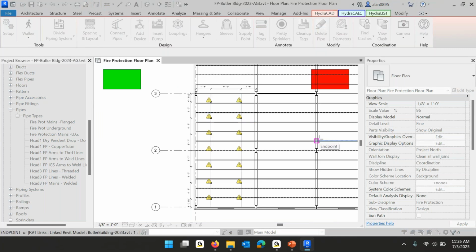And the dimensions help, and the fact that the sprinklers are showing up in that little bay area, I think is good confirmation of what's going on. It's making my layout with a 6 feet apart with just a bunch of sprinklers. Every sprinkler is 6 feet apart. Correct. Is it possible it's going for 100 square feet per sprinkler instead of 130?